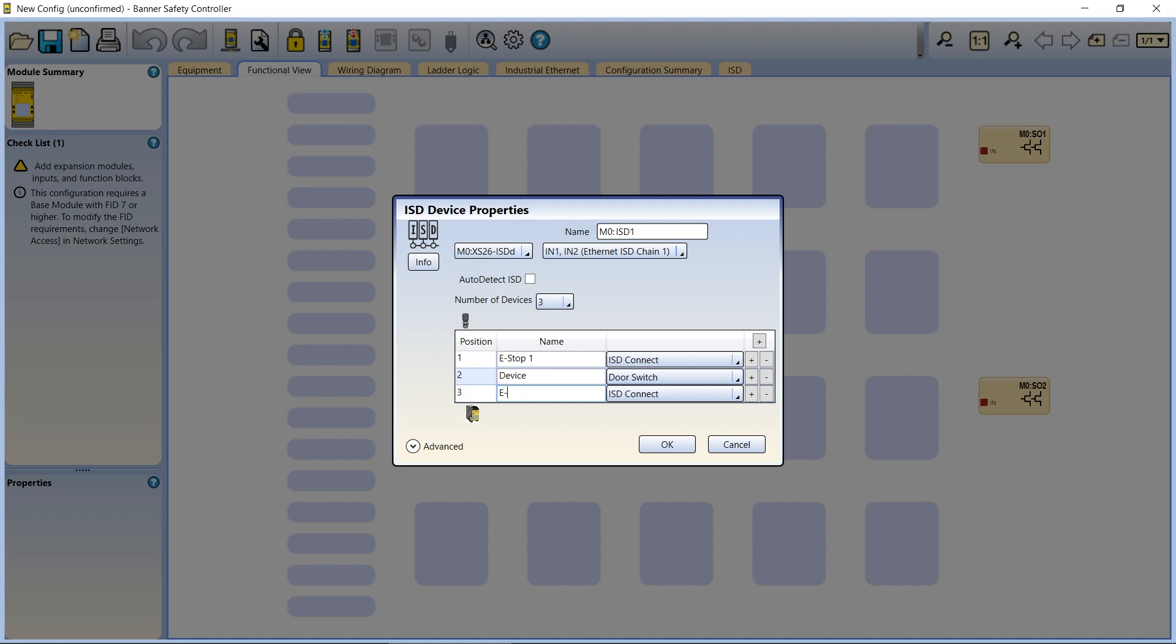For this method, the devices are numbered with device number one positioned closest to the terminating plug and increasing the closer they are to the controller. The images in the ISD properties window provide a helpful reminder of this order.